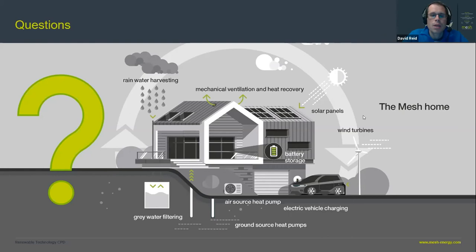So the answer to that is that air source heat pumps do need to defrost. They will typically defrost two or three times an hour. The heat exchanger that the air goes over is below freezing, so you'll get condensation onto that heat exchanger, and then that condensation will eventually freeze. If you did nothing about it, that would actually block the heat exchanger and stop the heat pump from working. So they do reverse cycle and then defrost. That is all taken into account in the coefficient of performance figures that are published.